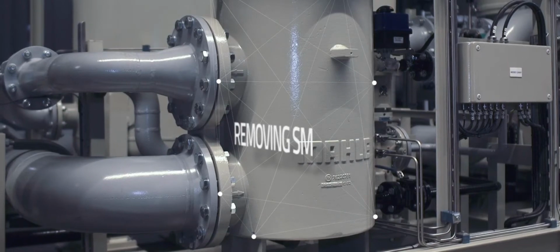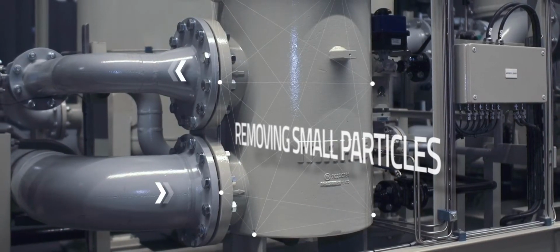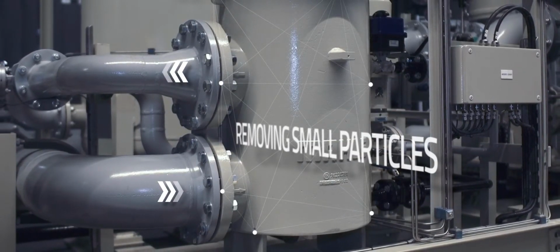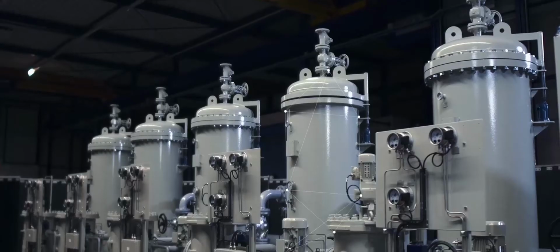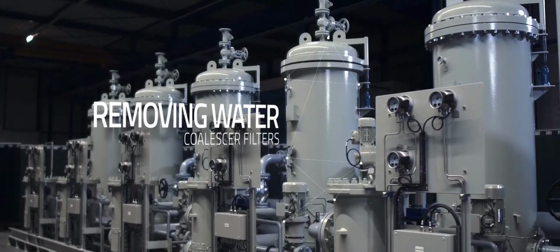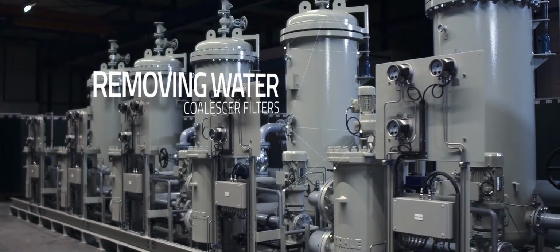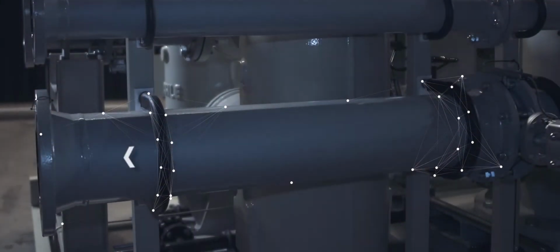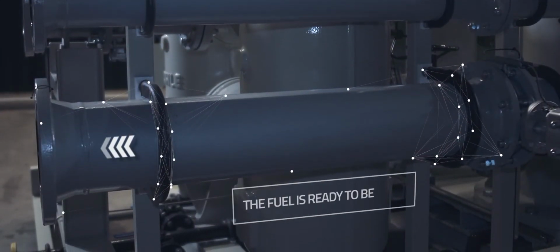After the strainer, the fuel passes the back flush filter to remove the smaller particles. The next and final step is the removal of water in the coalescer filters. After the coalescer filter, the fuel can leave the fuel treatment plant and is ready for usage in the power plant.